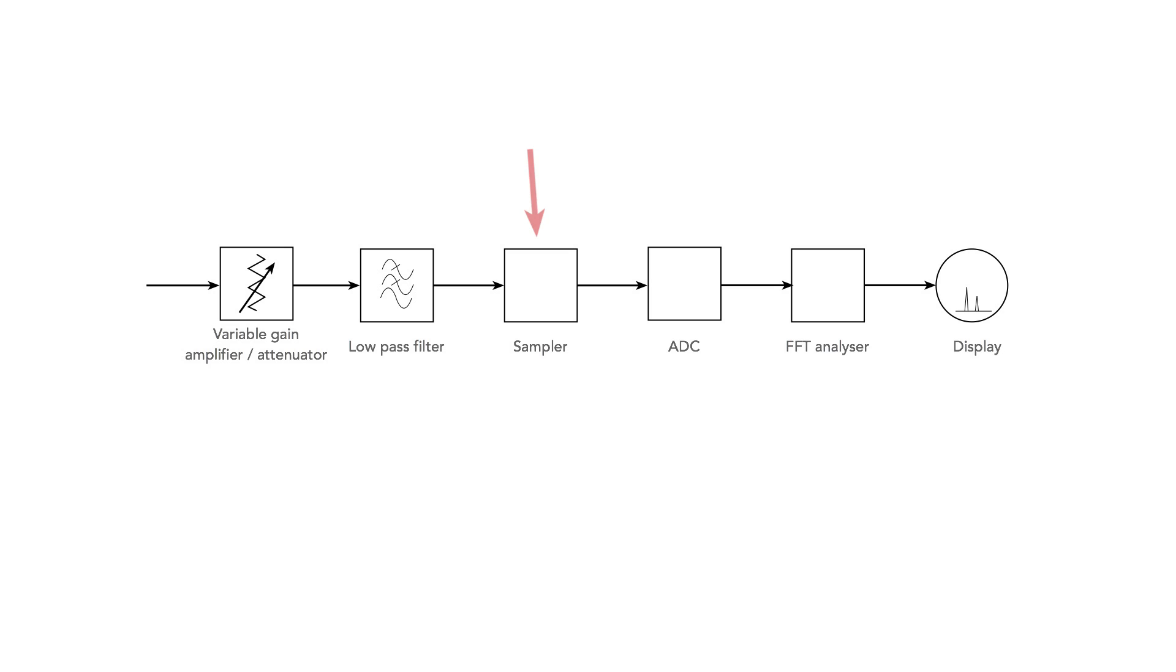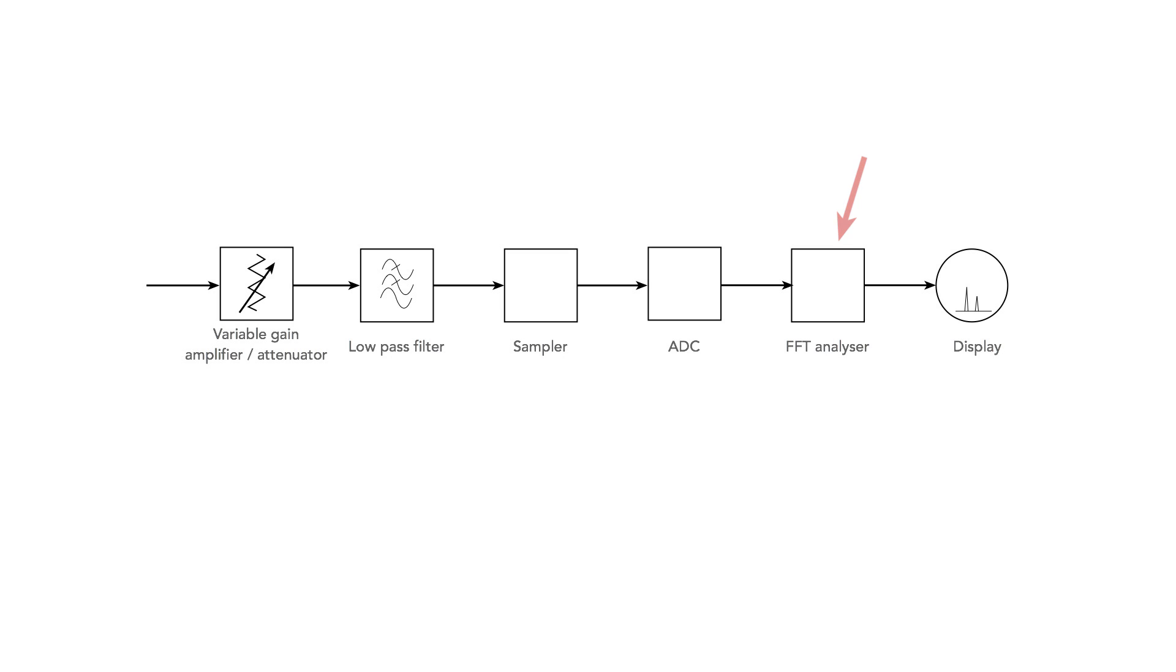The signal is then sampled at regular intervals and the results pass to an analog to digital converter. This converts them into a series of voltage samples that are passed to the digital signal processor that uses the fast Fourier transforms to undertake the required calculations and processing. Finally, the signal is passed to the display where the required output can be seen on a screen.